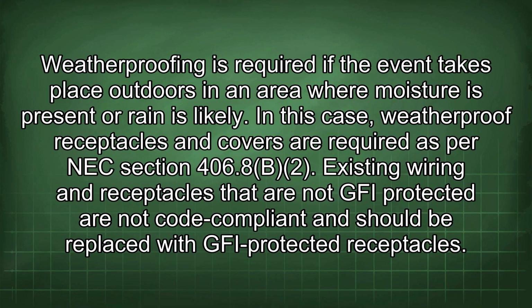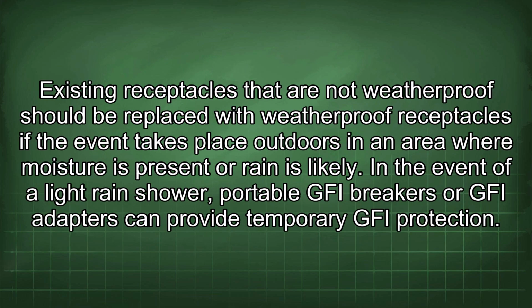In this case, weatherproof receptacles and covers are required as per NEC section 406.8(B)(2). Existing wiring and receptacles that are not GFI protected are not code compliant and should be replaced with GFI protected receptacles. Existing receptacles that are not weatherproof should be replaced with weatherproof receptacles if the event takes place outdoors in an area where moisture is present or rain is likely. In the event of a light rain shower, portable GFI breakers or GFI adapters can provide temporary GFI protection.